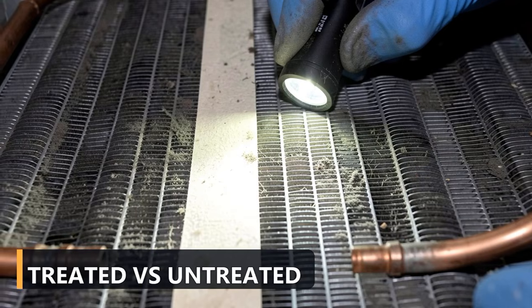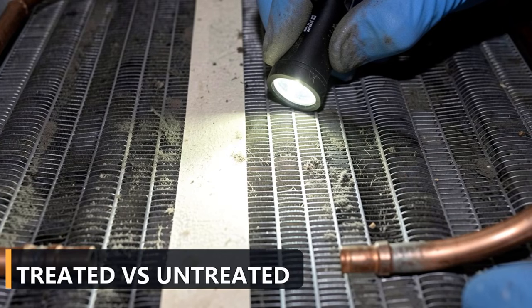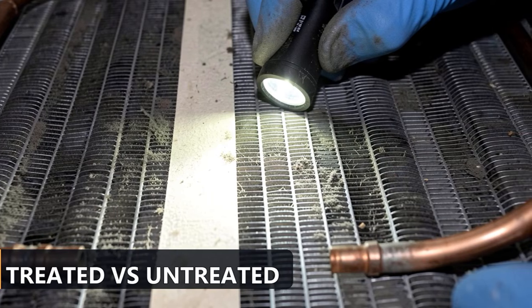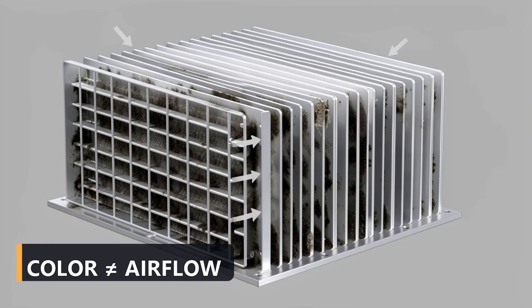Now compare the treated stripe with the untreated stripe using a flashlight from behind the coil. Both still block much of the light. The peroxide changed the color, but it did not reopen the passages. Until air can move through the entire depth of the coil, the problem remains.